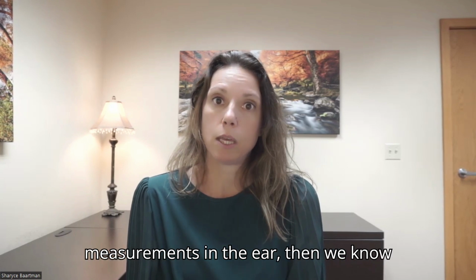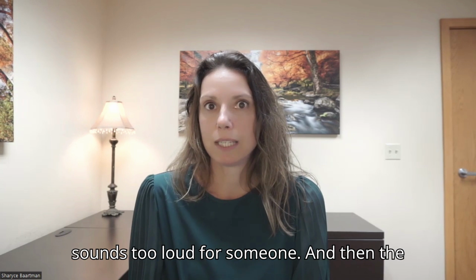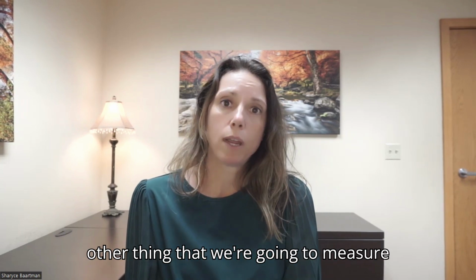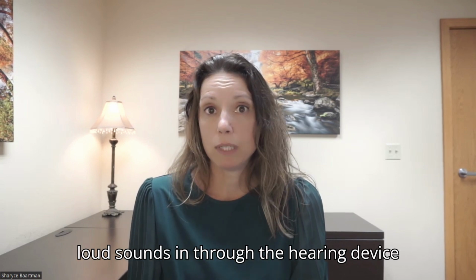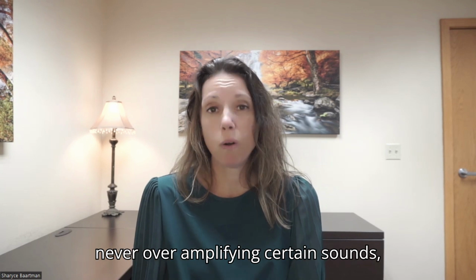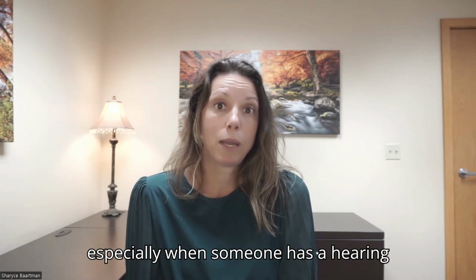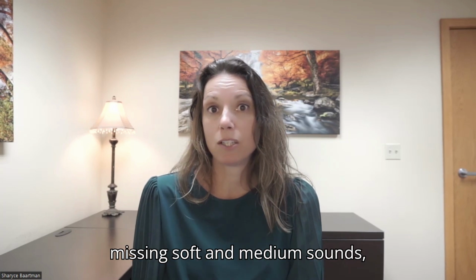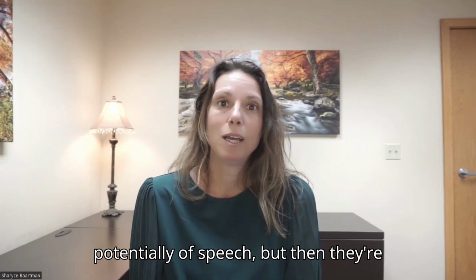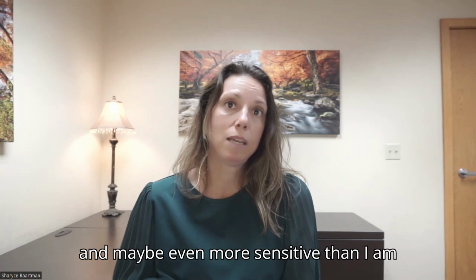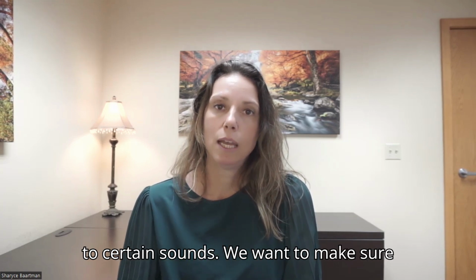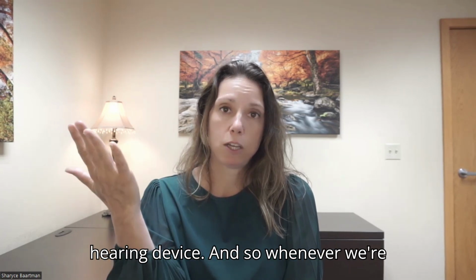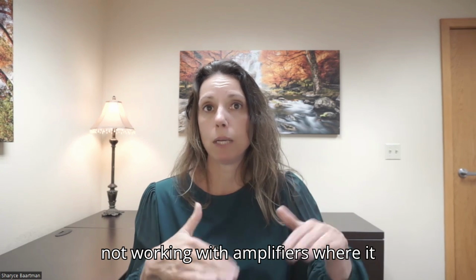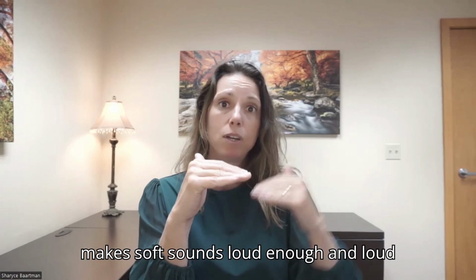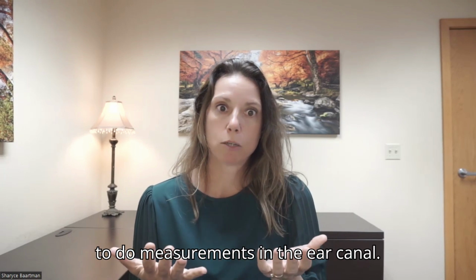If we do measurements in the ear, then we know that we're not going to amplify certain sounds too loud for someone. The other thing that we're going to measure is the maximum output. We're going to put loud sounds in through the hearing device, and we want to make sure that we are never over amplifying certain sounds, especially when someone has a hearing loss. What I find is not only are they potentially missing soft and medium sounds of speech, but they're also going to be sensitive to loud sounds, and maybe even more sensitive than I am to certain sounds. So we want to make sure that we're limiting the output of the hearing device. Whenever we're working with hearing technology, we're not working with amplifiers that amplify everything. We're working with a compression circuit that makes soft sounds loud enough and loud sounds tolerable. So we're always going to do measurements in the ear canal.